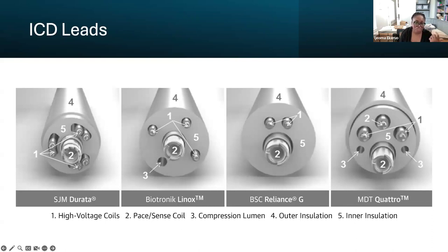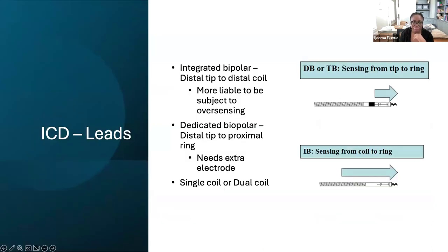They'll have your high voltage coil, you'll have a pace sense coil, a compression lumen sometimes - in Biotronik they have that, and in Medtronic they have it, not necessarily in Boston or Abbott/St. Jude. There's an outer insulation that sits on the outside of the pace and sense coil so that it's able to detect things with fidelity. And then also you have your inner insulation that surrounds all the lead components.